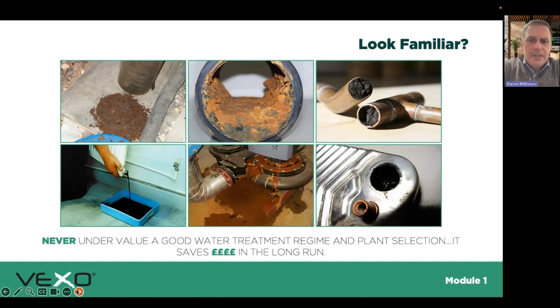In the long term, unfortunately, we'll see effects like reduced flow rate, changes to delta T, or complete blockage of pipework and plate heat exchangers. We're seeing huge numbers of HIU units installed now, and a lot of retrofit designs use plate heat exchangers to protect new equipment from, say, an old heating system. But that doesn't help the building owner if the secondary side of the plate heat exchanger becomes fouled - they won't get the heat delivered that they need, especially as we move to more zero carbon technologies.